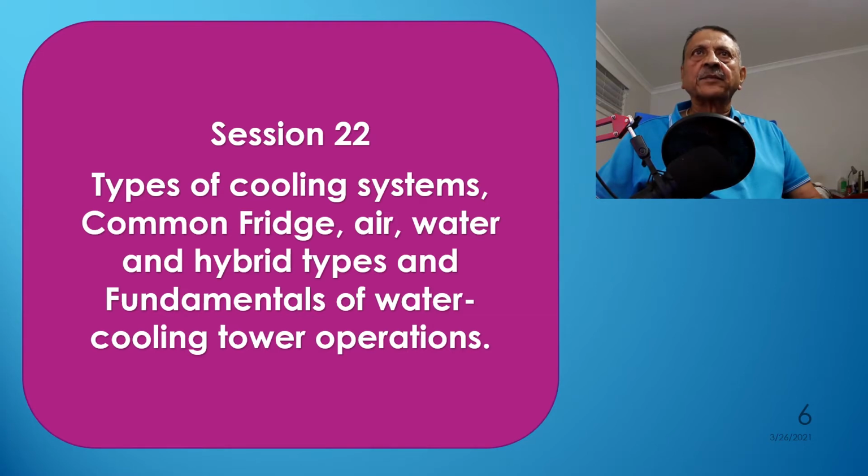The water actually becomes contaminated in a water treatment system as it brushes the air and collects dust, bacteria, algae, spores, etc. At the same time, water is lost through evaporation and drift, which must be replaced, as well as water lost due to total dissolved solid buildup. The water must also be treated to remove the organic component buildup, as well as reduce the microbiological growth, both for health and longevity of the operating systems.